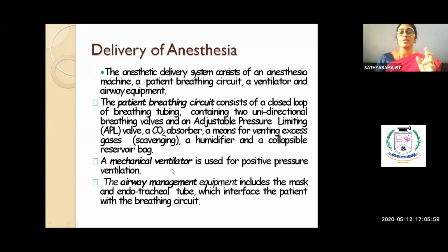So they have all these valves, the APL valves, which you can adjust. Then the CO2 absorber, so we would have seen it on the anesthesia machine with that soda lime down, right? It picks up and absorbs the entire carbon dioxide. And then a scavenging system, so whatever is being given out from the patient has to go back to the atmosphere. So we have a scavenging system which takes these off into the environment.